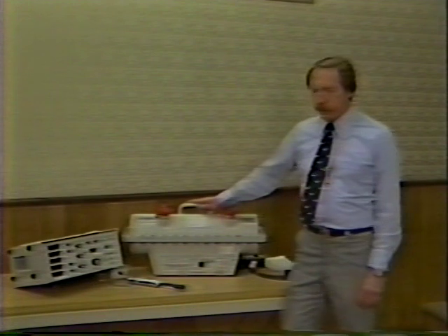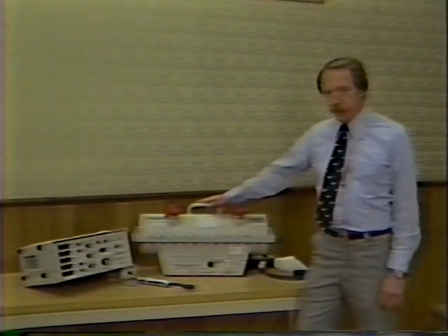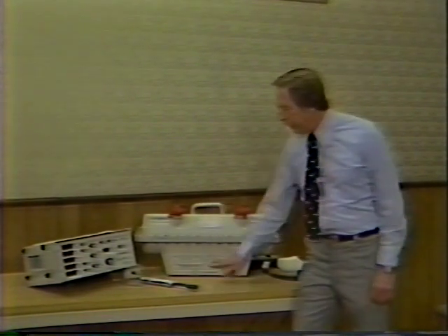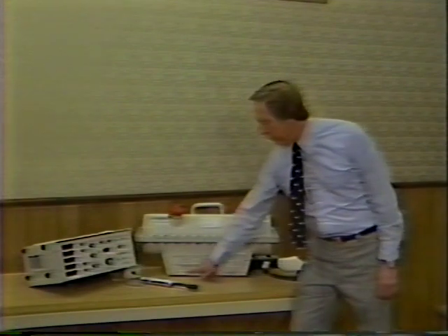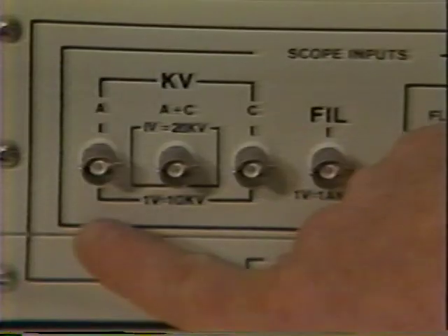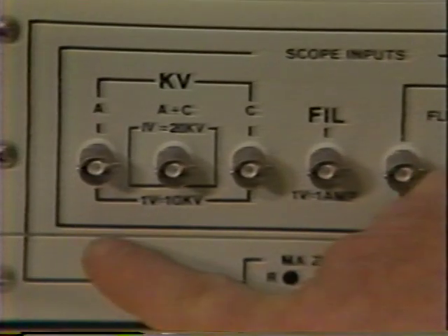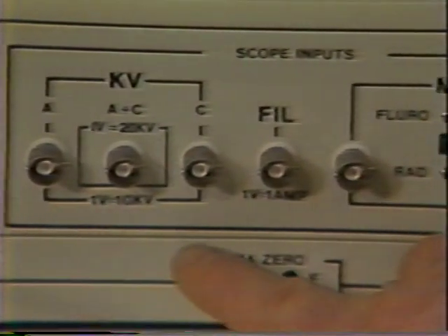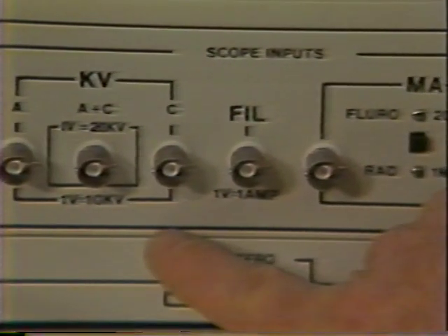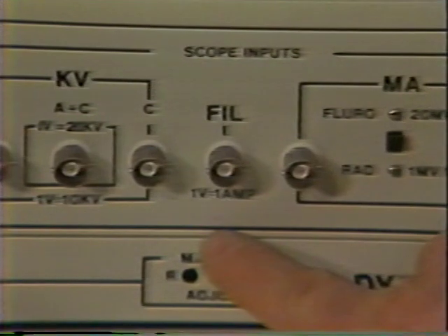This is the Dynalyzer 3 high voltage unit, or sometimes called the bleeder. It has 5 coaxial connectors on the front. The first connector is for reading anode to ground on the scope. The second one, cathode to ground. We can read filament current. We can also read MA.